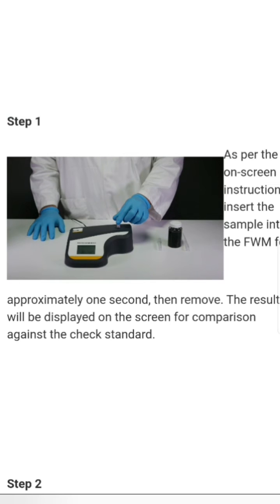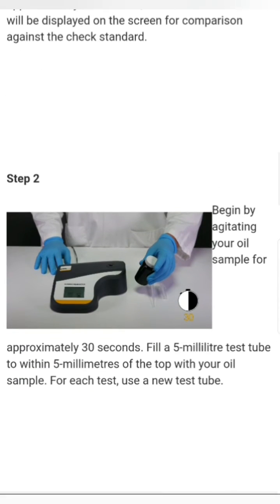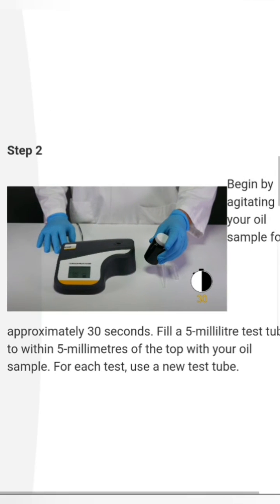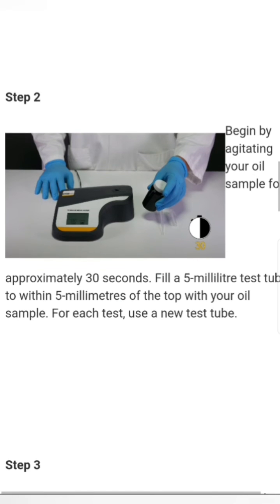Step two: begin by agitating your oil sample for approximately 30 seconds. Now fill a 5-millilitre test tube to within 5 mm of the top with your oil sample. For each test we have to use a new test tube — you can see here the new test tube and the dropper. We will fill it now.